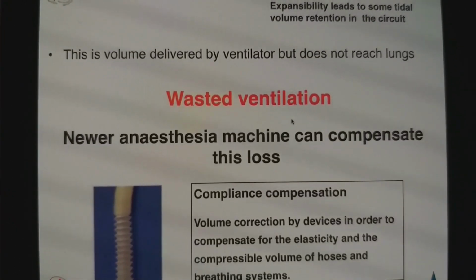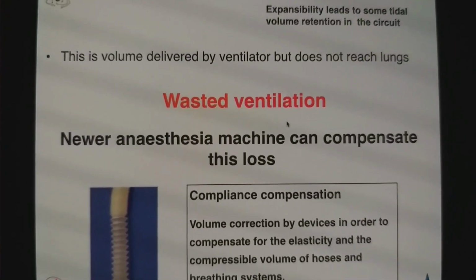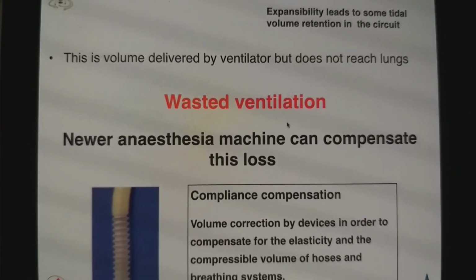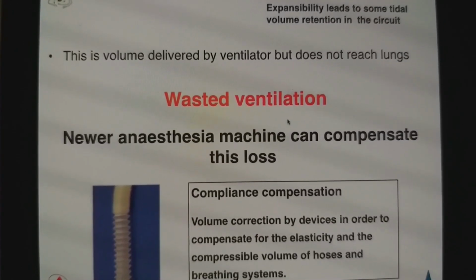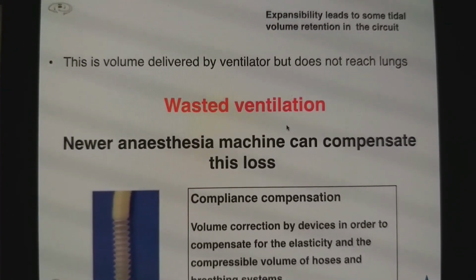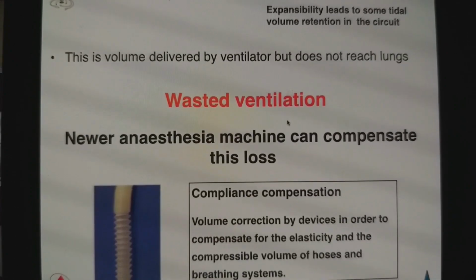Newer anesthesia machines can compensate for this. This is called compliance compensation. Here, there is volume correction by the device in order to compensate for the elasticity and compressible volume of hoses and the breathing system.